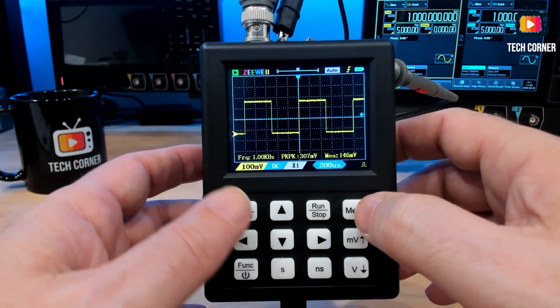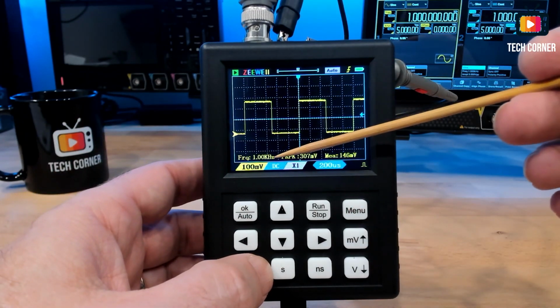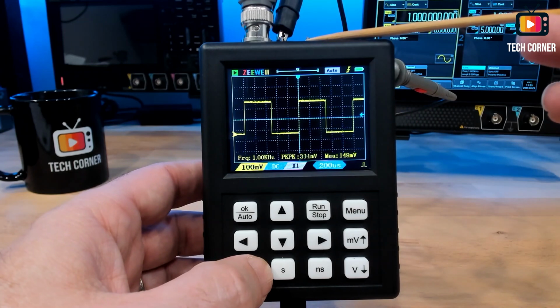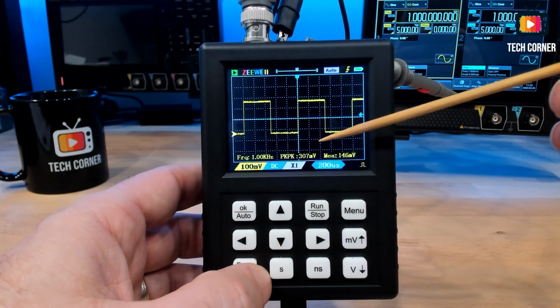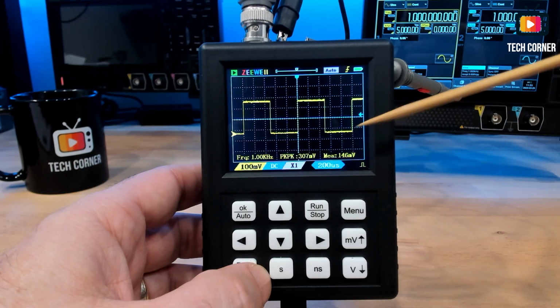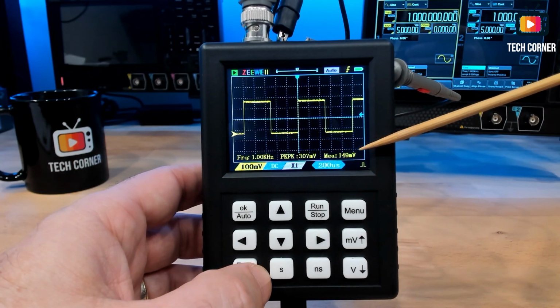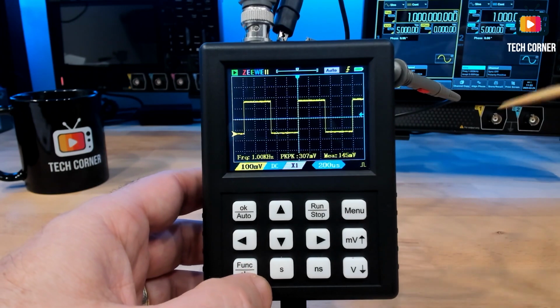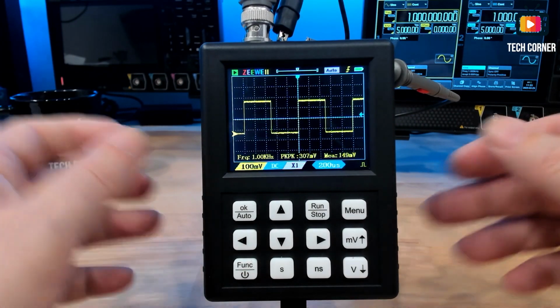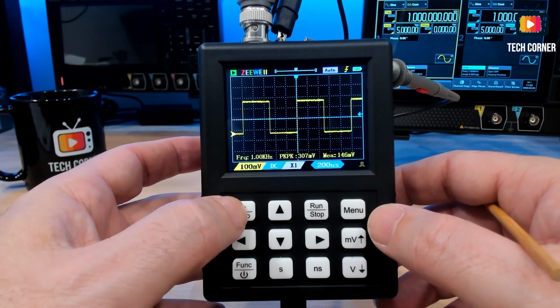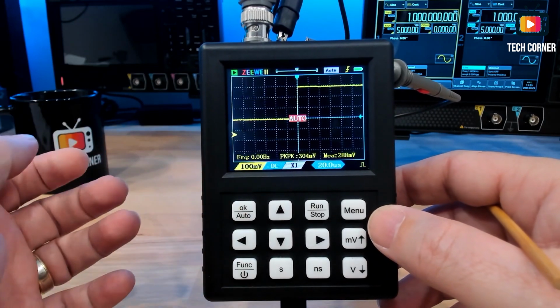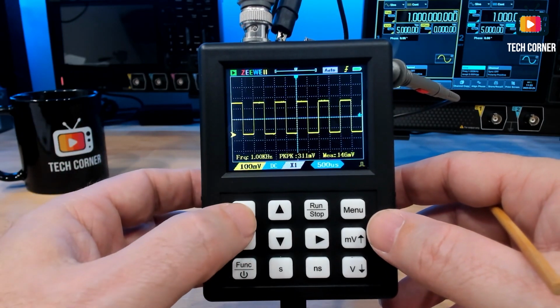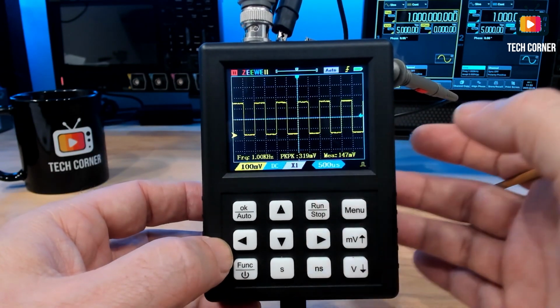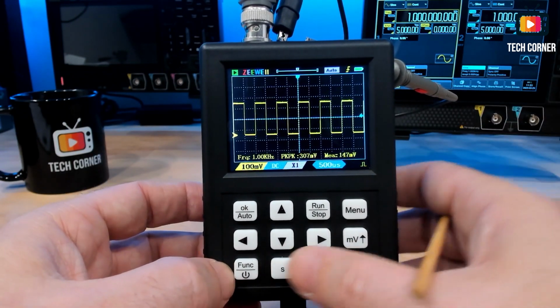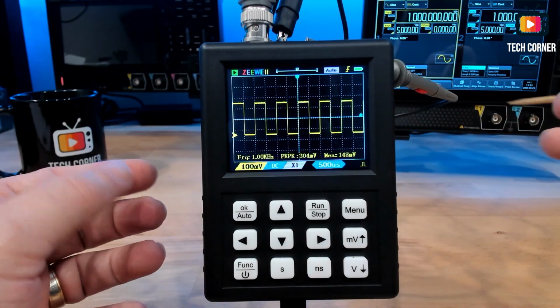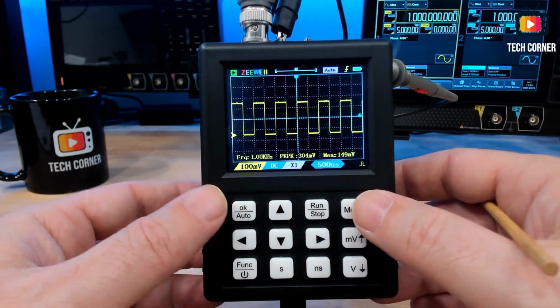Now that we have this on the screen, we can see that the measurement is with 1 kHz frequency. That's the normal from this output for calibration. Also we have a peak-to-peak of 300 millivolts and the mean voltage about 140-50 millivolts. Okay? Well, in terms of the screen and the keys in the keyboard are more or less this. You have the auto. As you can see, it was really fast to update, and also the run and stop that I previously showed. We already saw the movement functions, and we have 2 special keys right now. Well, 1 special key and the menu key.